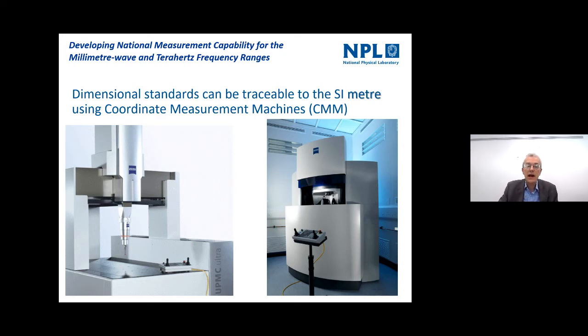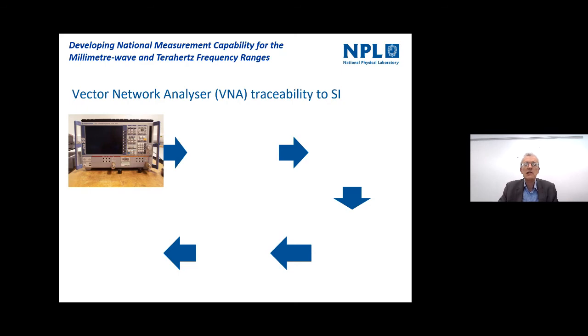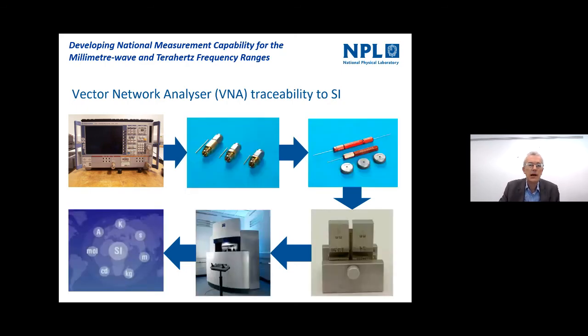So if we now present that traceability flow, it looks something like this. You can see the network analyzer gets its assurance from the airlines, which get their assurance from the plug and ring gauges, which link to the gauge blocks in the bottom right, which links to the coordinate measurement machine, which links us back to the international system of units. There's no circularity in this route of traceability. We're going back, linking the network analyzer to absolute scientific constants defined by our international system of units.